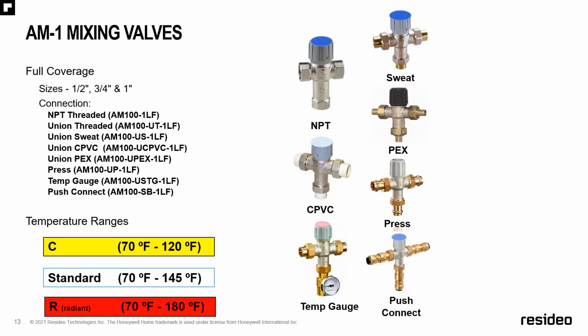Hydronic applications can have multiple temperatures in one system, as we kind of talked about. One end of the house could be heated with baseboard heating that requires higher temp, anywhere between 160 to 180 degrees at times. And then you have an indirect water heater that could run at a different temperature. And then you could have a slab in a bathroom or a family room that has a heated floor. Well, you don't want to run that radiant floor at anything over 160. It obviously depends on the design and what kind of heat emitter, if you're using plastic or onyx rubber or copper, it all depends. But we do have an R mixing valve to separate those two temperatures within that system.